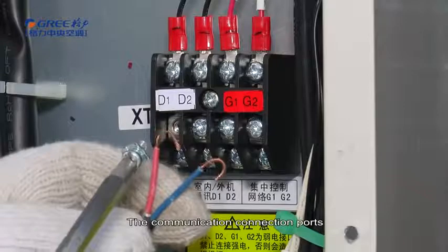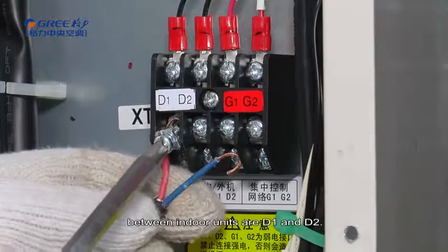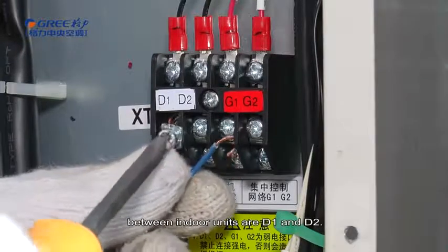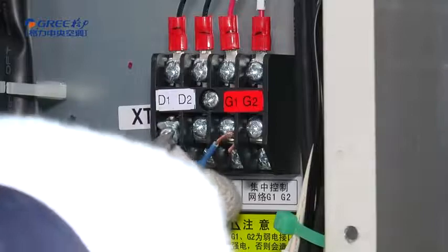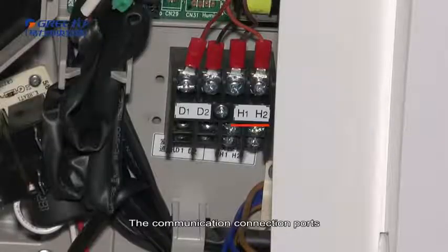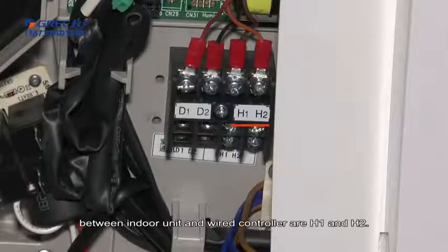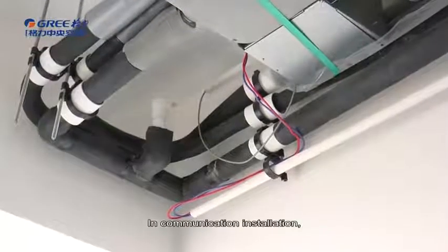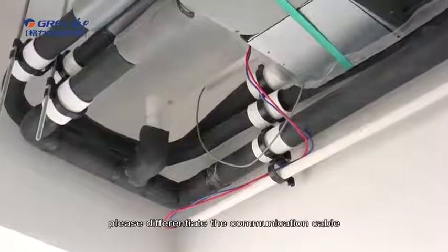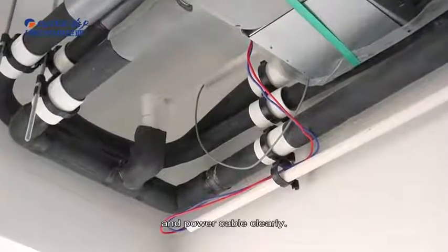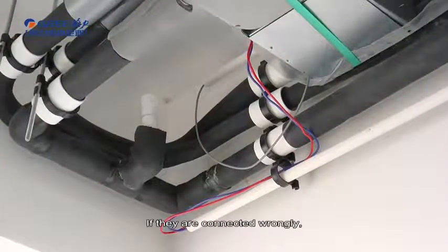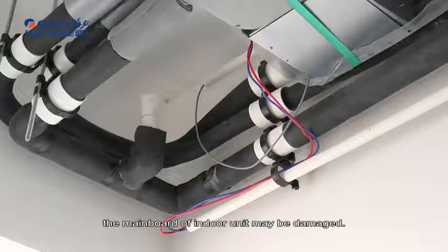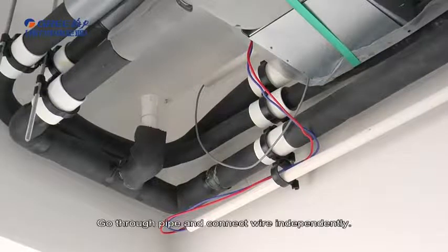Installation of communication cable. The communication connection ports between indoor units are D1 and D2. The communication connection ports between indoor unit and wire controller are H1 and H2. In communication installation, please differentiate the communication cable and power cable clearly. If they are connected wrongly, the main board of the indoor unit may be damaged. Go through pipe and connect wire independently.